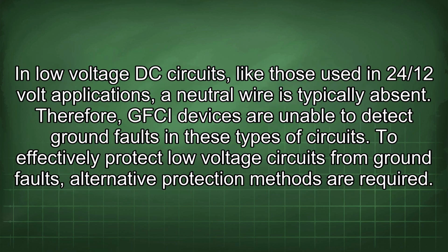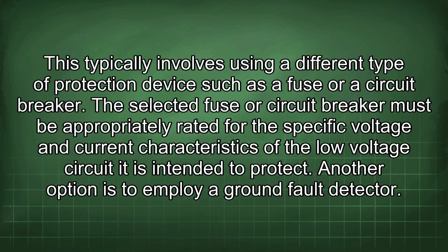In low-voltage DC circuits, like those used in 24/12 volt applications, a neutral wire is typically absent. Therefore, GFCI devices are unable to detect ground faults in these types of circuits. To effectively protect low-voltage circuits from ground faults, alternative protection methods are required. This typically involves using a different type of protection device such as a fuse or a circuit breaker. The selected fuse or circuit breaker must be appropriately rated for the specific voltage and current characteristics of the low-voltage circuit it is intended to protect.